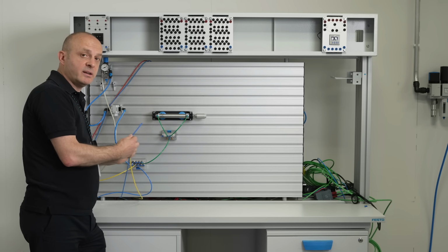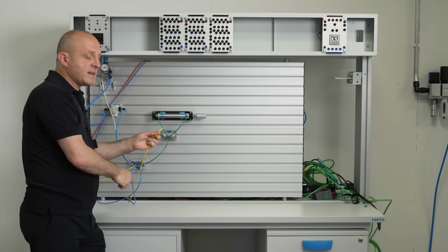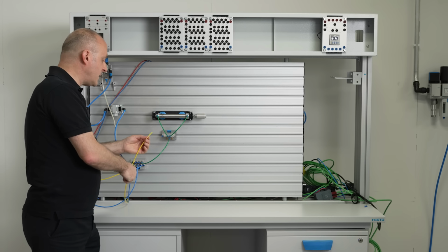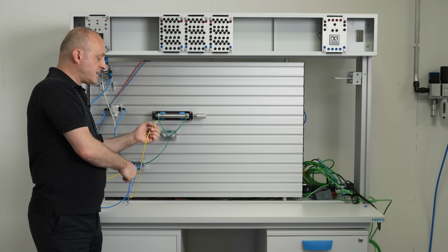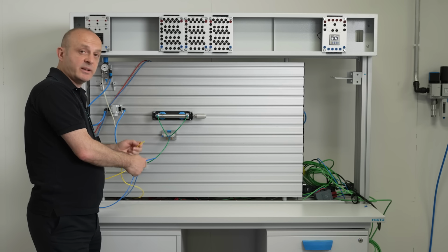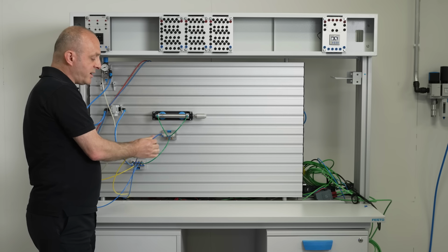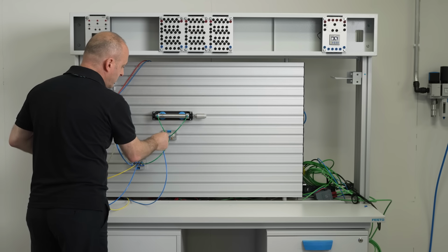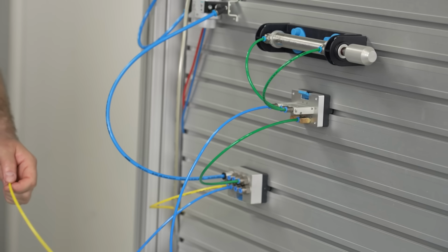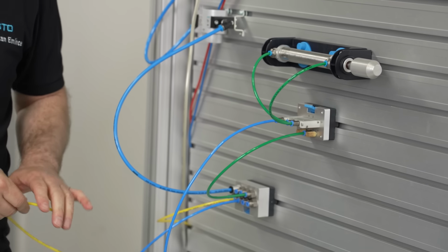We can clearly hear air coming out. On this tube, air is not coming out. First, we reckon this tube is the one causing the problem, not the advanced cylinder, not this one. Okay, I will try the blue one first. Air is coming out. The cylinder is not advancing. Surprising, isn't it?